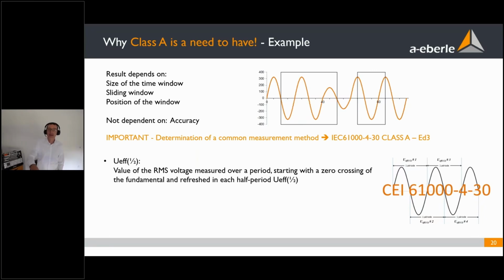In the Class A, it is always like that the voltage and the current is measured over a period, starting with a zero crossing of the fundamental, and is refreshed every half period. This is just one small thing which gives you the feeling why there is a need to have a Class A device and not use any other devices.